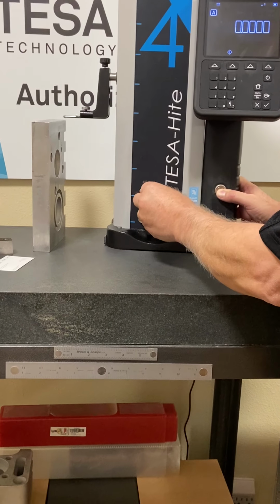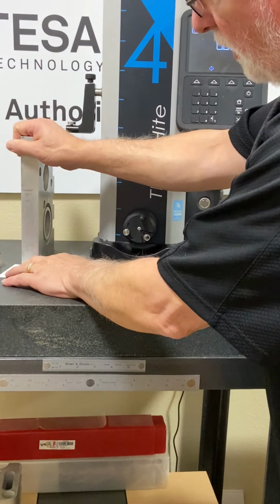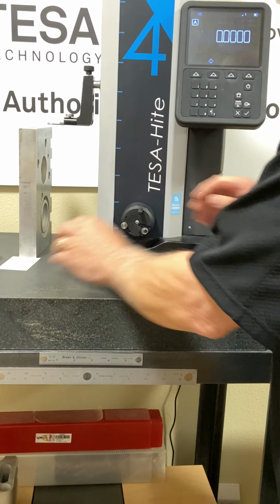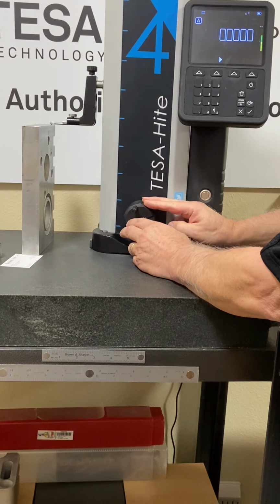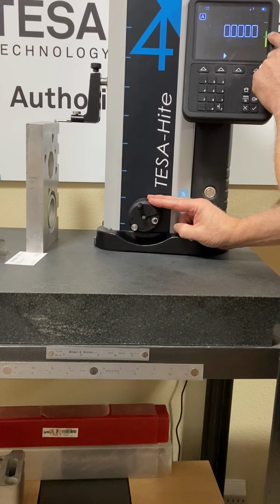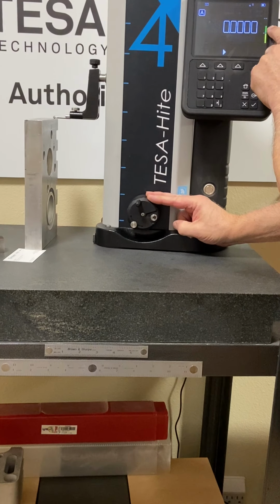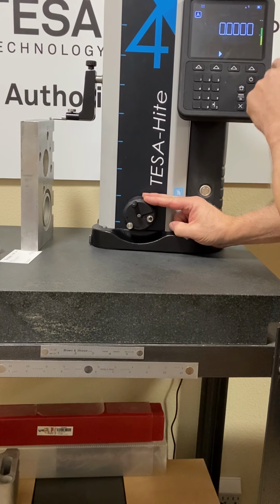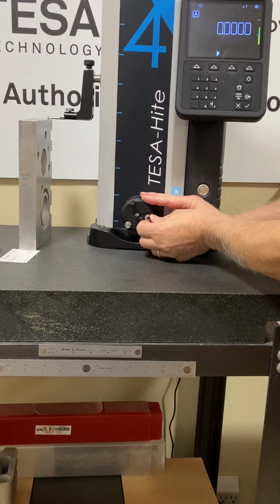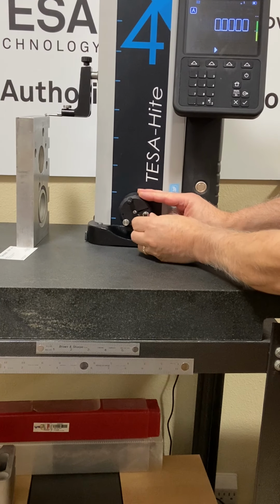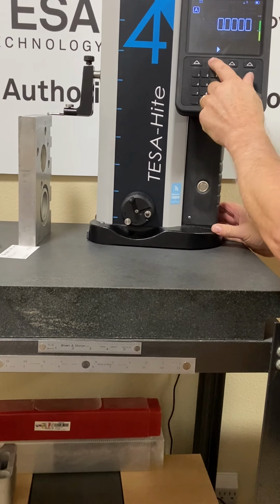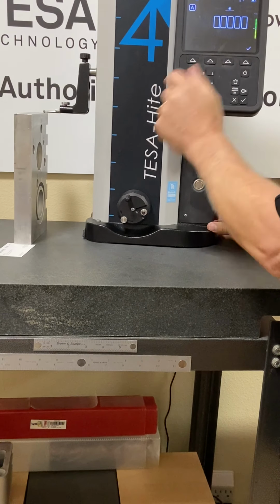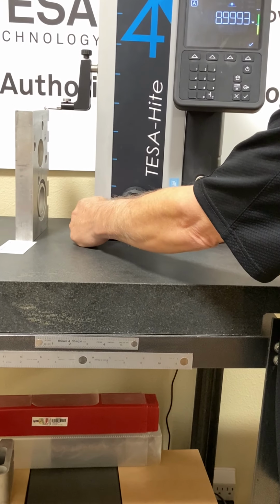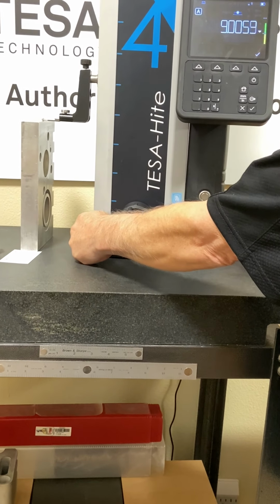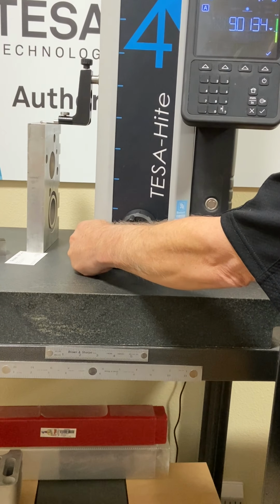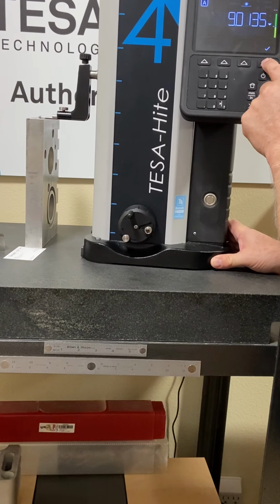And then I'm going to come up here on my workpiece. I'm going to put a little shim underneath of it. I come down here. I've got pressure on my probe right now. I want to be in the green spot up here between these 2 lines. And then I just take and thumb tighten it. So now it's locked. I hit my go or enter key. And now I can just tram the workpiece, and I can either move the height gauge or move the part. It doesn't matter. When I'm finished, I hit the check mark.